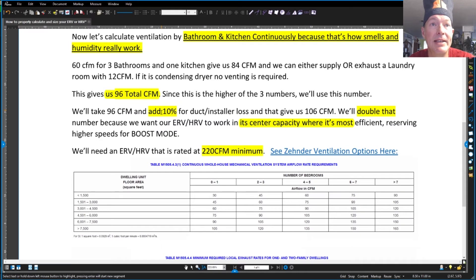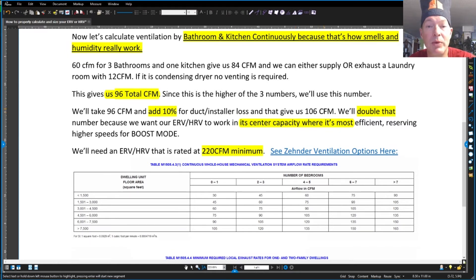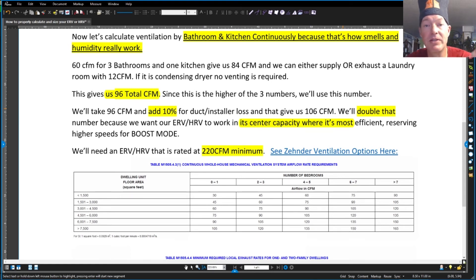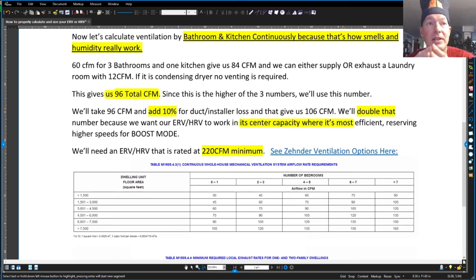We'll add 10% to that for duct installer losses and general losses, which gives us around 106 CFM. Then we want to double that for capacity — if we're taking a shower or there's something that needs to get out faster, when we hit a ramp-up switch, we want that bathroom's 20 CFM to double to 40 or more. That way, we distribute that point source load and energy much faster so it doesn't have a lot of time to condense around there.